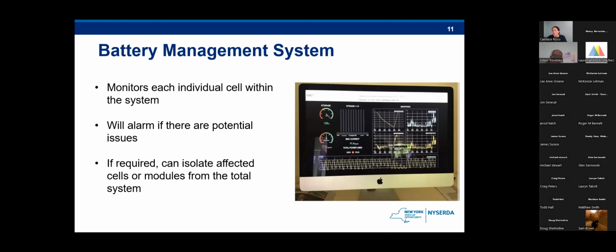And it can also monitor each individual cell within the system and make sure that it's operating properly. So if there's any issue outside normal cell, module, or rack operating characteristics, it can be isolated. It can isolate the cell to avoid it damaging additional cells. So not only is it watching and making sure everything is operating properly, it can also manage and deal with any uncharacteristic issue that occurs within the system.